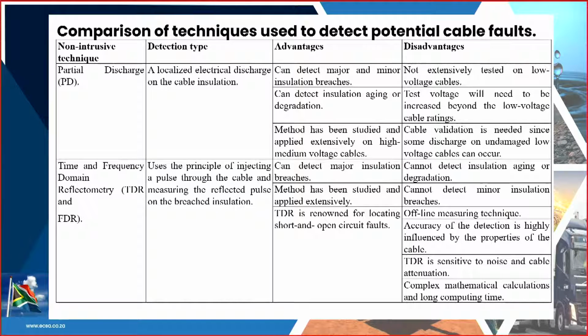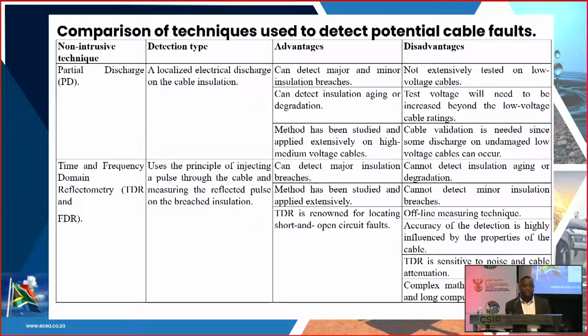I've identified three techniques, and due to time I won't exhaust the full list. First, partial discharge measurements: we send a high voltage through the cable and cable insulation, and if there is a discharge on the insulation, it means the insulation is compromised. This method has been studied extensively on high to medium voltage power cables, but not really on low voltage cables.